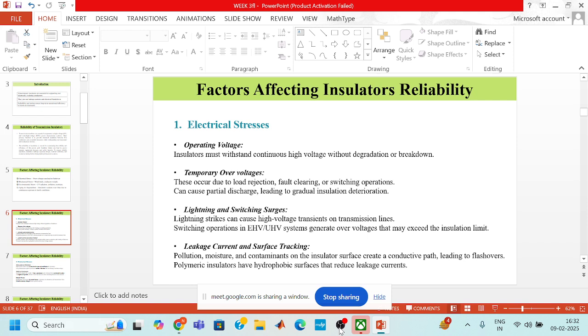So here are some details. Electrical stress depends on operating voltage, temporary overvoltage, lightning and switching surges, leakage current and surface tracking. For operating voltage, insulators must withstand continuous high voltage without degradation or breakdown. Second is temporary overvoltage. This occurs due to load rejection, fault clearing or switching operations. It can cause partial discharge leading to gradual insulation deterioration.